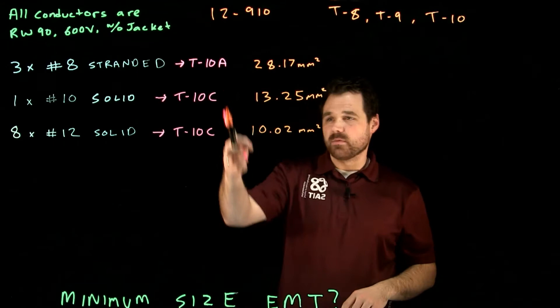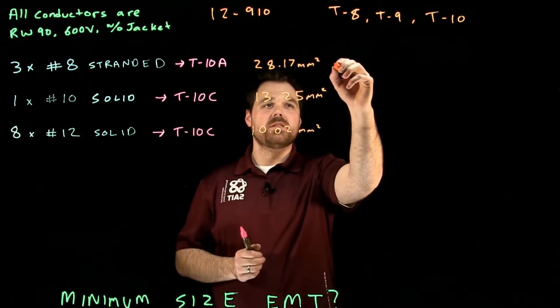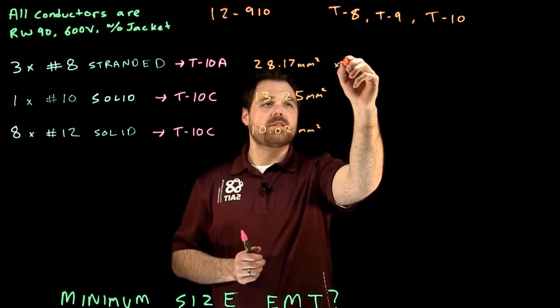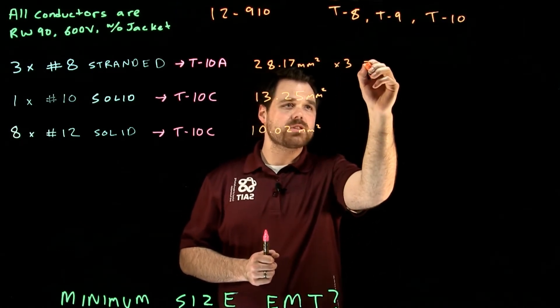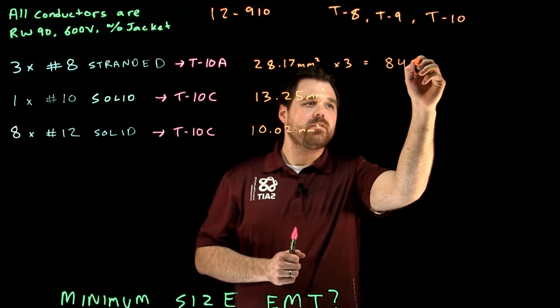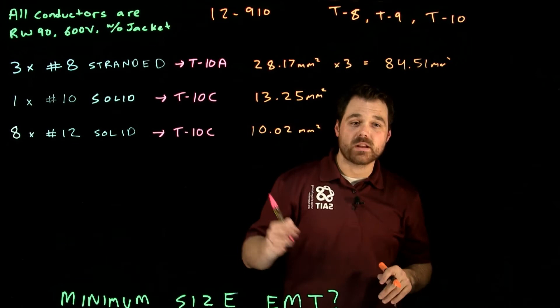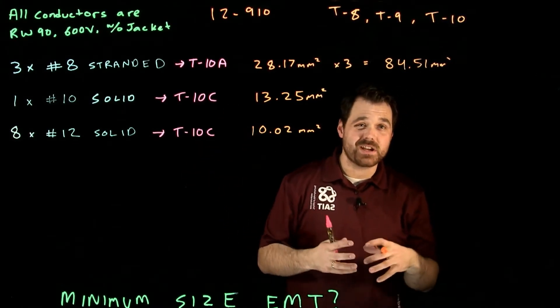So all this information came from table 10. Now what I want to do is I want to take this. I want to multiply this by three because I have three conductors. That's going to give me 84.51 millimeters squared. Now that's how much space my three number 8 strands are going to take up inside a conduit.